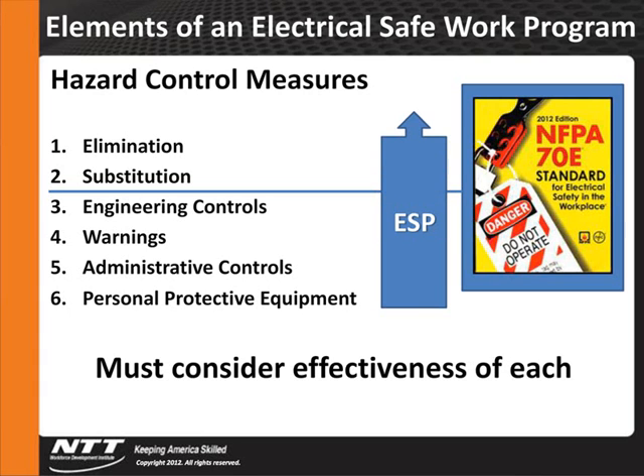Some examples today of following a more complete electrical safety program involving both elimination and substitution of equipment would be things like arc-resistant switchgear, or placing within adjustable trip breakers a maintenance trip setting that would lessen the exposure of a worker doing troubleshooting on downstream equipment. The electrical safety program must involve the first two, elimination and substitution, to be completely successful.